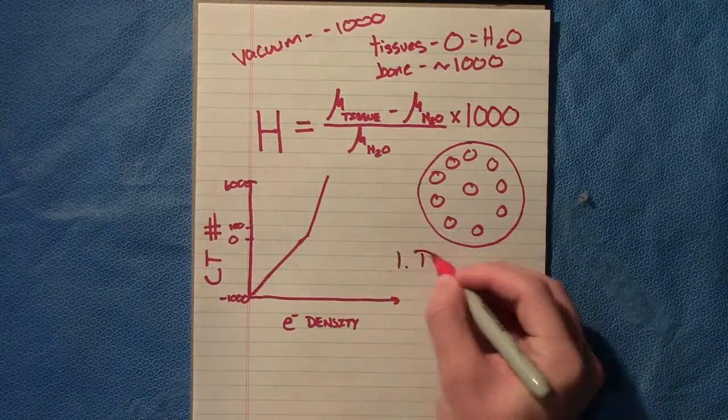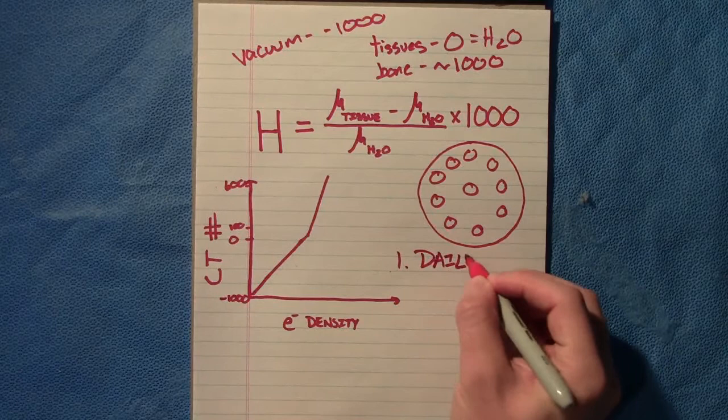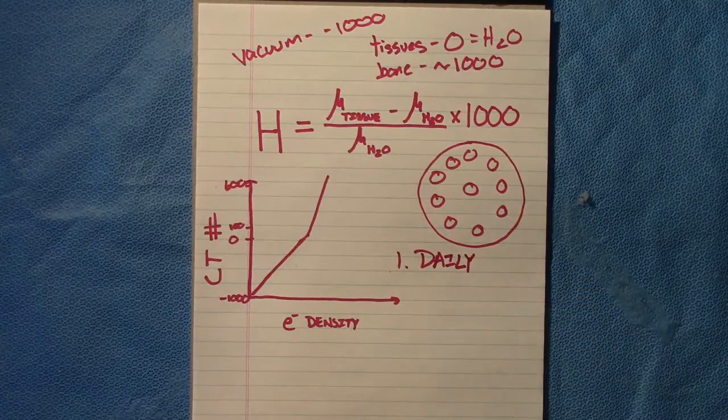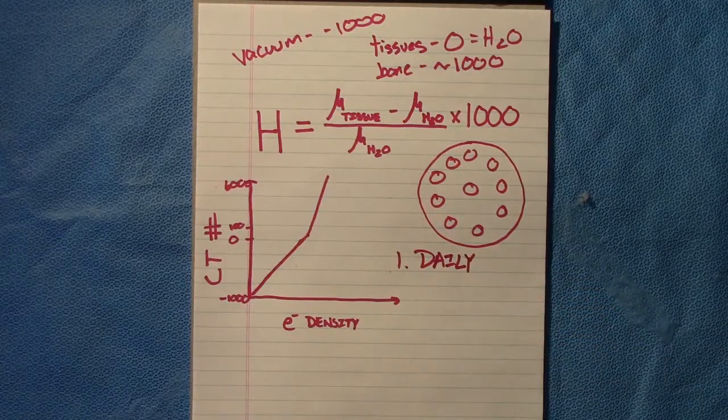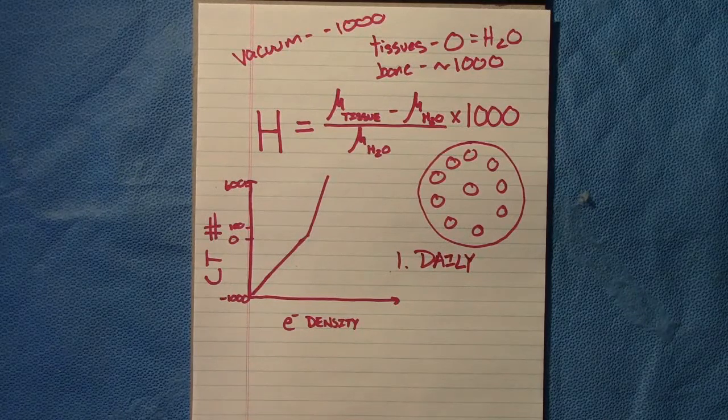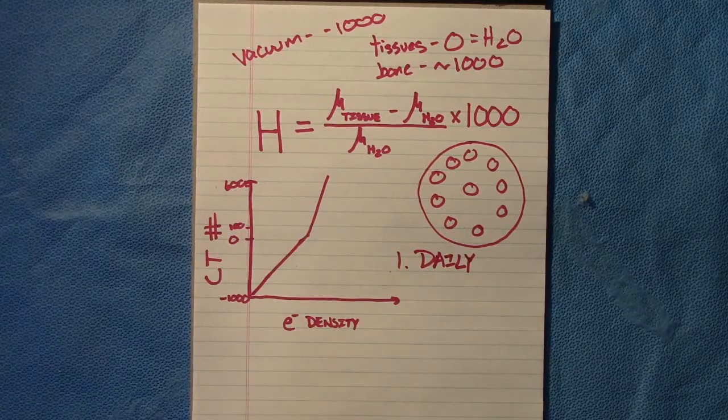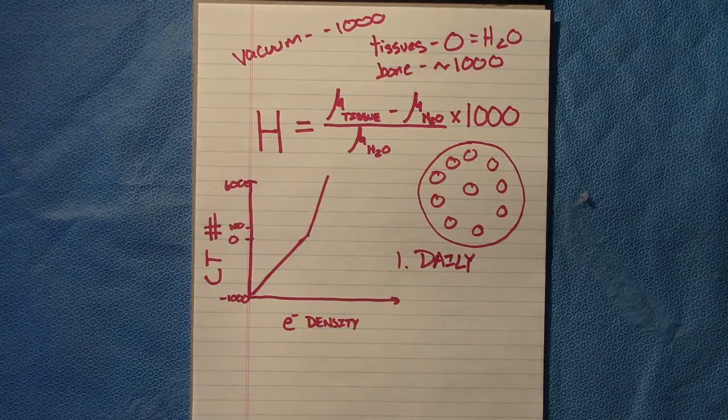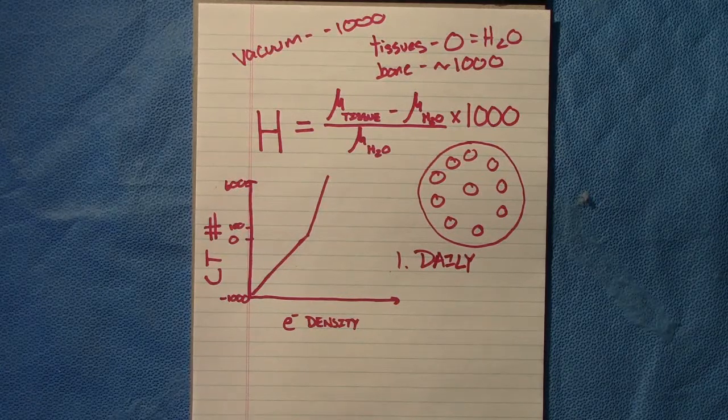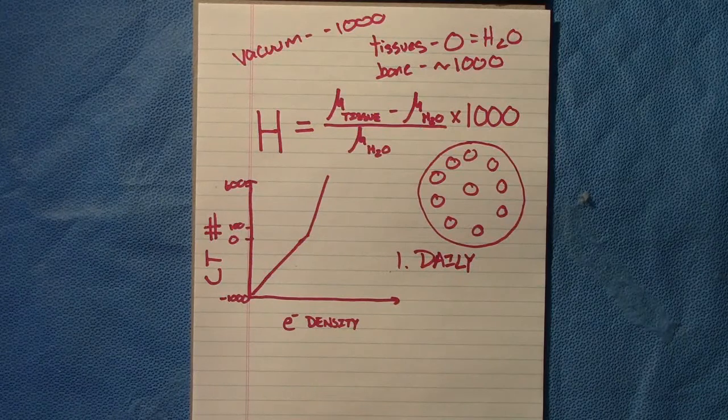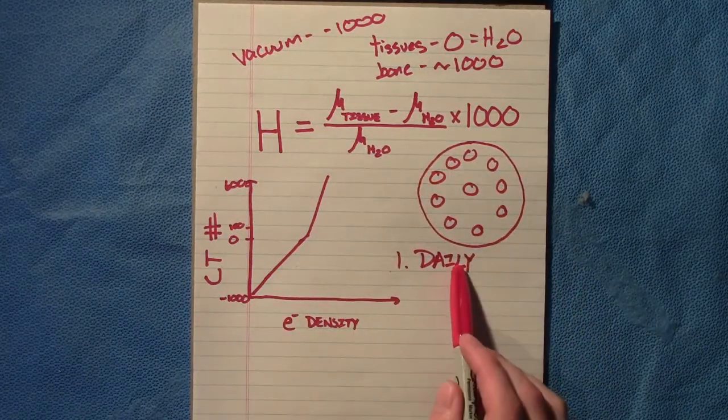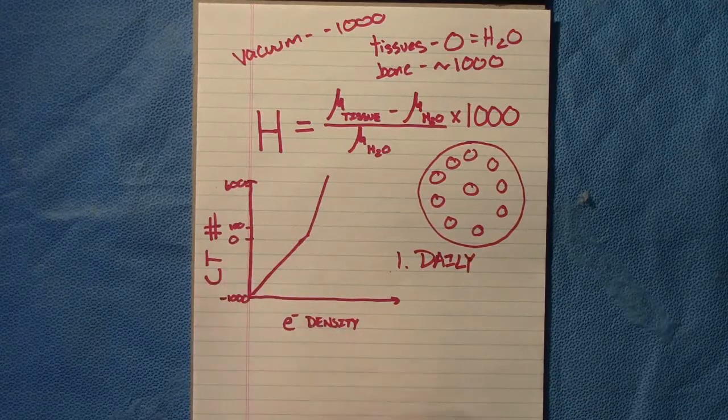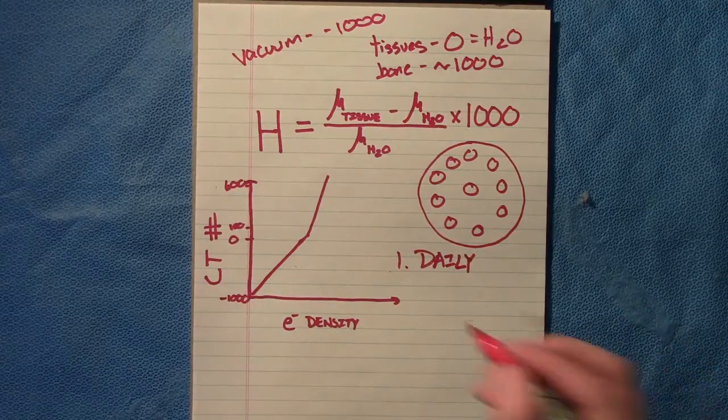The first test that we have daily: we scan a phantom and it has some plugs in it that we know what the CT number should be because we did that when we commissioned the CT. We test it—there's also other things such as lasers and positioning that we also test daily too, but for the realm of this discussion, the big thing is daily we do test CT number of water and the most common materials.